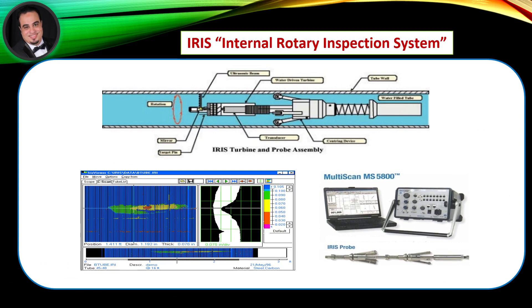As illustrated in the figures, the Internal Rotary Inspection System (IRIS) is used when a higher flaw detection and sizing capability is needed compared to other methods, but it is slower and thorough tube cleaning is required prior to inspection. IRIS can be used on both ferrous and non-ferrous materials and is most commonly used on carbon steel tubes.